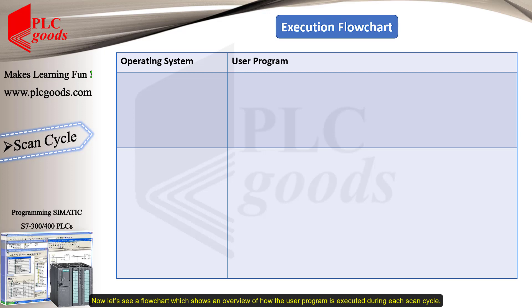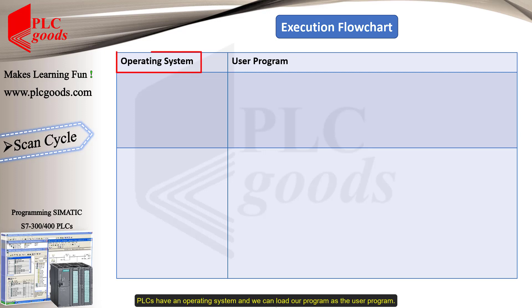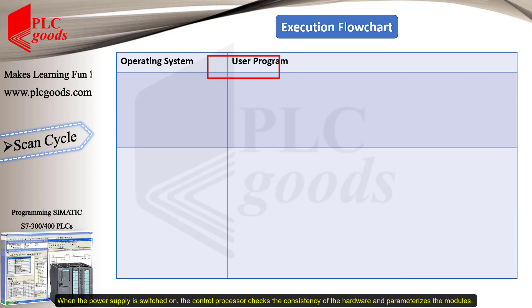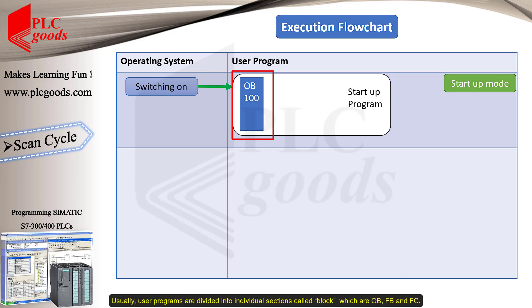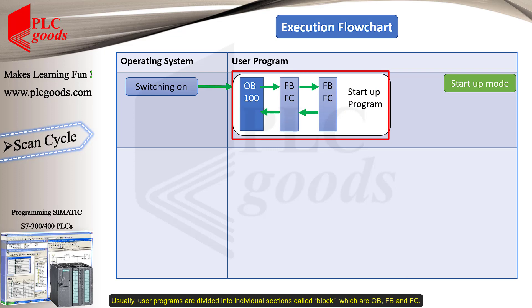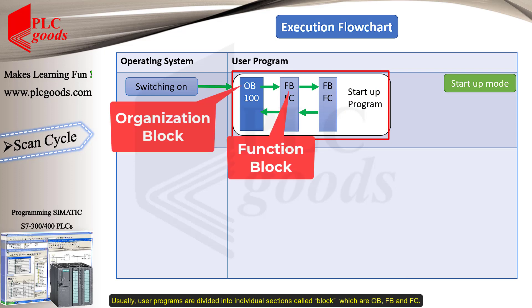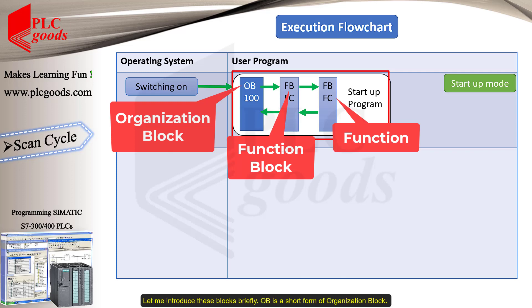Now, let's see a flowchart which shows an overview of how the user program is executed during each scan cycle. PLCs have an operating system and we can load our program as the user program. When the power supply is switched on, the control processor checks the consistency of the hardware and parameterizes the modules. Then, the startup program is executed once, if present. Then, the user programs are divided into individual sections called blocks, which are OB, FB, and FC.